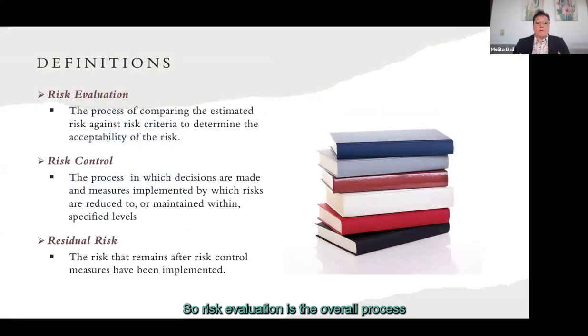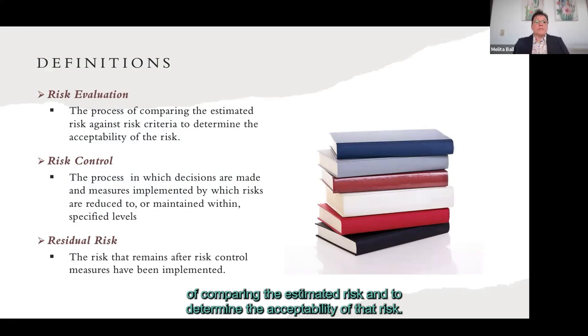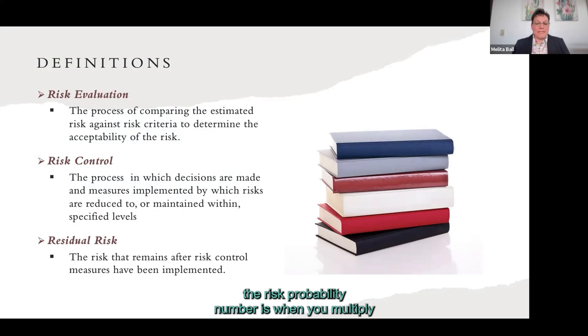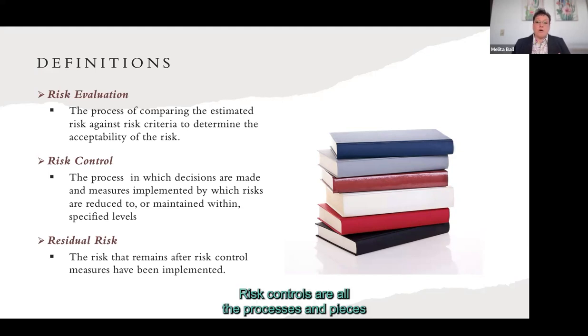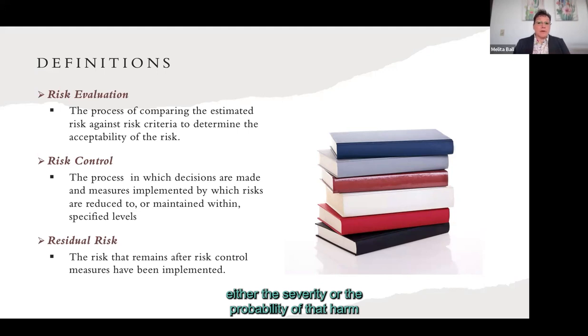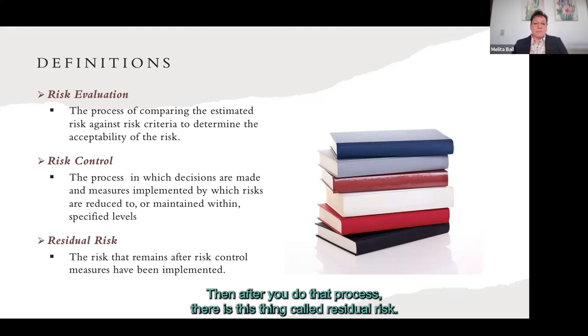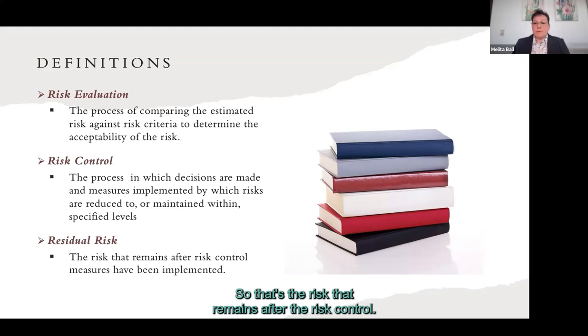Risk evaluation is the overall process of comparing the estimated risk against criteria to determine its acceptability. Once you calculate the RPN — the risk priority number — you determine whether it falls within your organization's defined framework of acceptability. Risk controls are all the processes and parts that define how you'll reduce either the severity or probability of harm. Residual risk is what's left after all risk controls have been applied — you then evaluate it again to confirm it's within the acceptable framework.